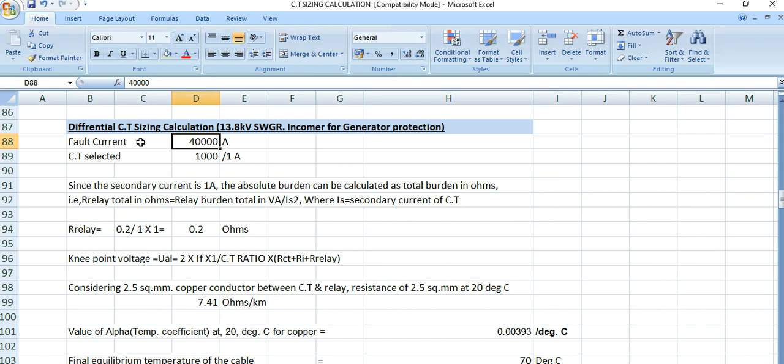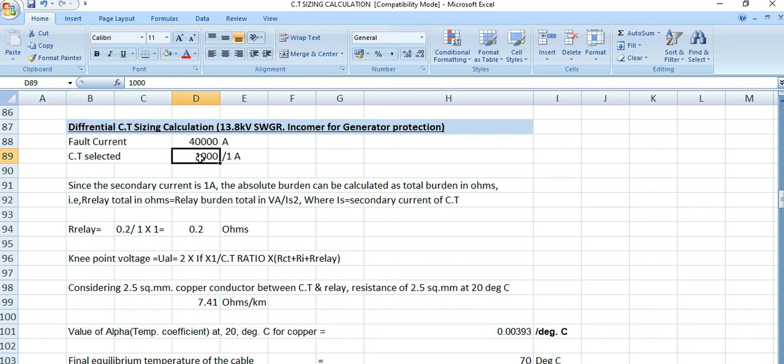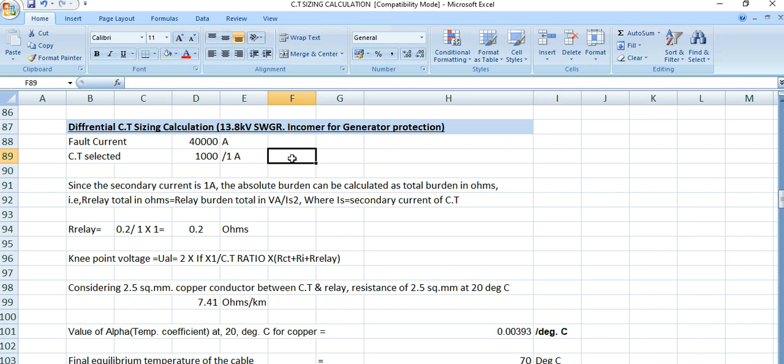In this case, the fault level is 40 kilo ampere, so the fault current is 40,000 ampere. For the differential protection we have selected a 1000/1 ampere CT, so the secondary side is 1 ampere. One important thing: for differential CT we need to select PS class CT. For protection CT we may consider 5P20 or 5P10, but for differential protection this is a special purpose CT which requires PS class.